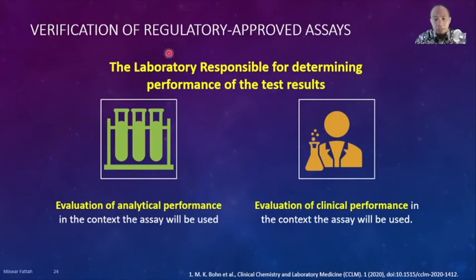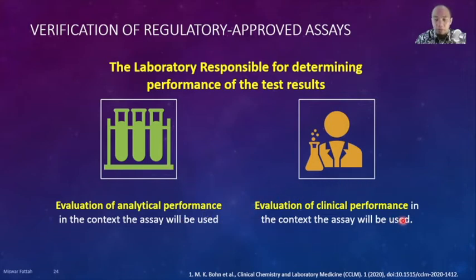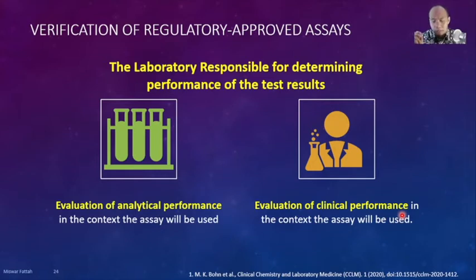The laboratory is responsible for determining performance of test results — evaluating analytical performance and clinical performance. During evaluation, the selected assay should be assessed by verifying whether it meets the manufacturer's claim and whether it meets the laboratory's set requirement based on assay use. Ideally, the assay should be evaluated in two parts: analytical performance and clinical performance.